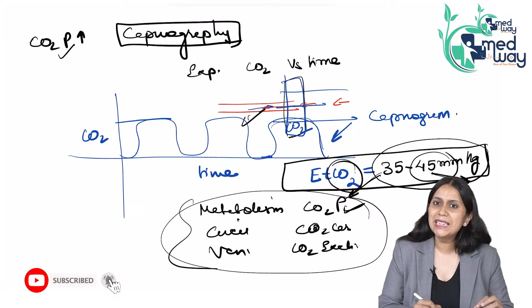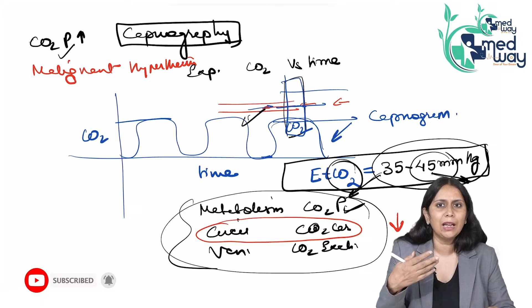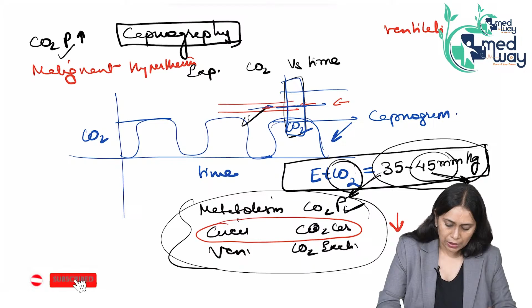Now, if the circulation is increasing, no change in CO2 will happen because there is a fixed CO2 produced in the body. But if the circulation decreases, the CO2 value will decrease. If the ventilation increases, hyperventilation, CO2 will go out of the blood very quickly. So the CO2 pressure in the blood will decrease, and that is what is depicted in the expired carbon dioxide. So the EtCO2 value will also decrease.